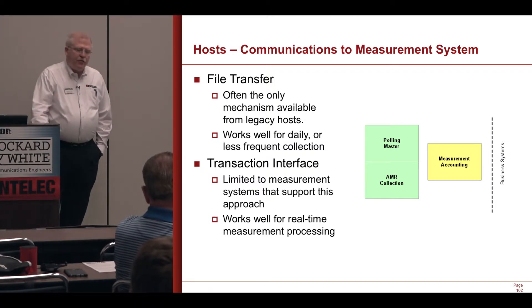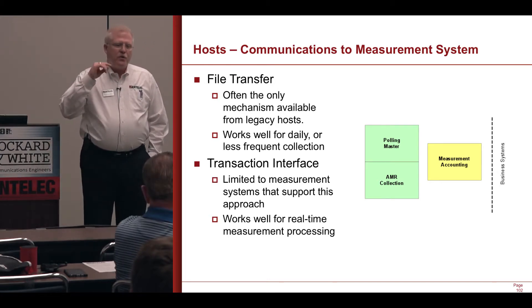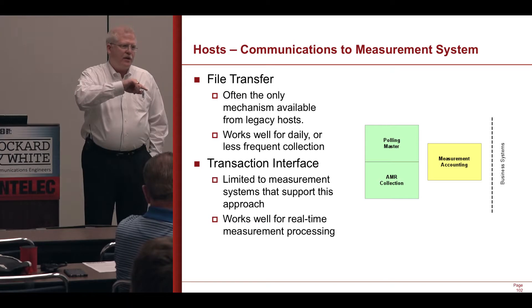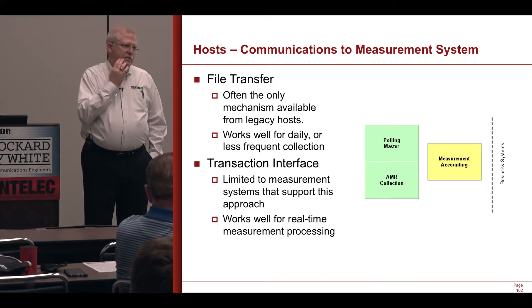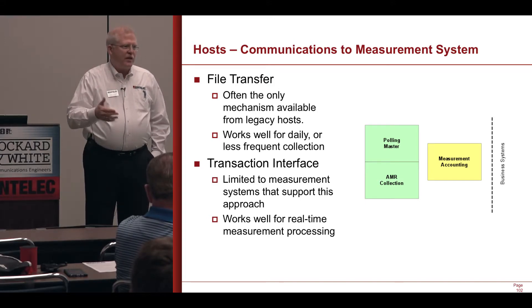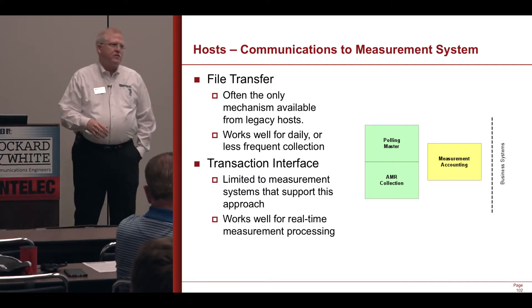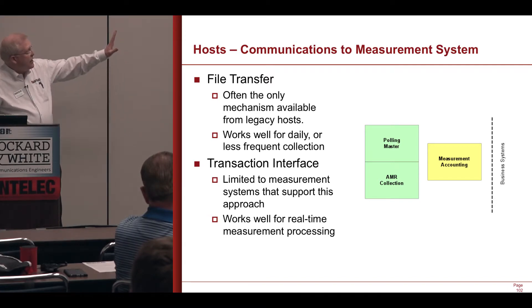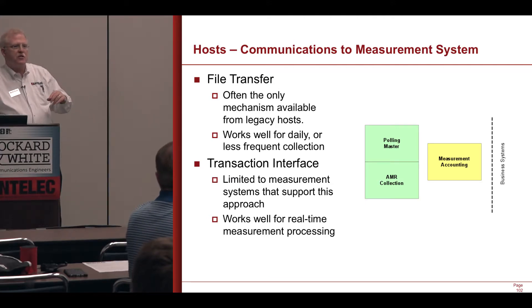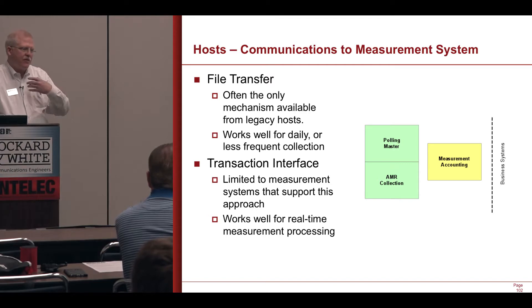When moving measurement data, if a SCADA system involves measurement data collection, we do not take the measurement data — the full audit trail — through the HMI. We take it directly into the measurement accounting system. There's really no value in the HMI for all of that data; that value is only useful in the back-office measurement system. That kind of data movement is oftentimes file transfer, because most back-office measurement systems — FlowCal, PGAS, etc. — read data in via specified file formats.